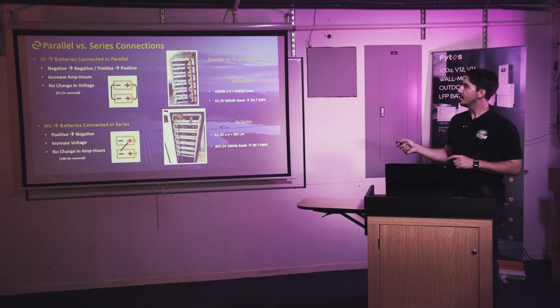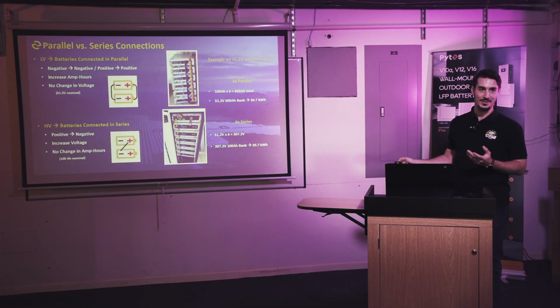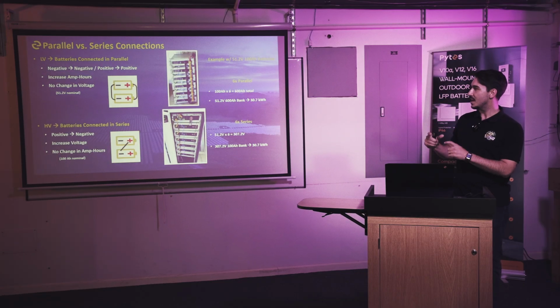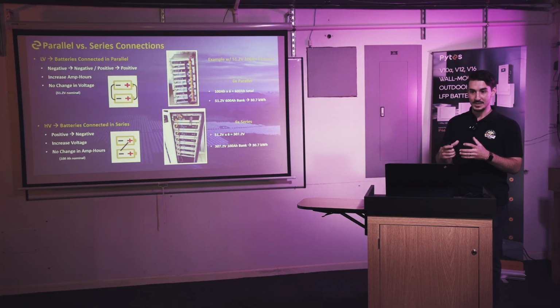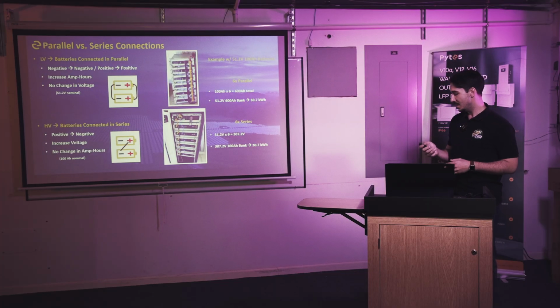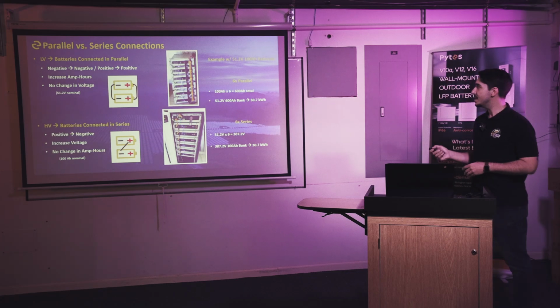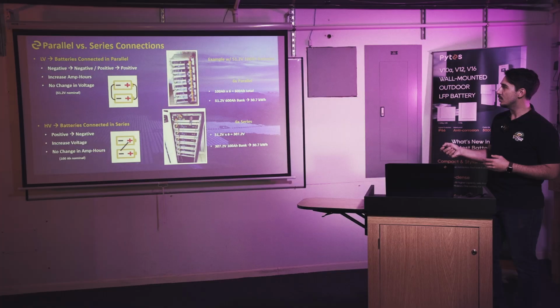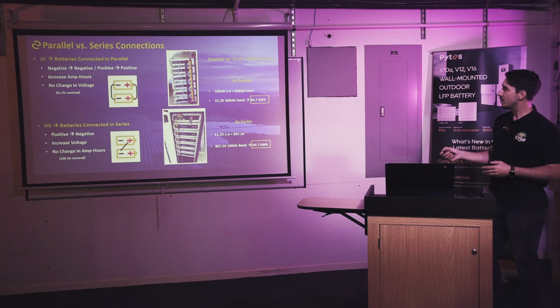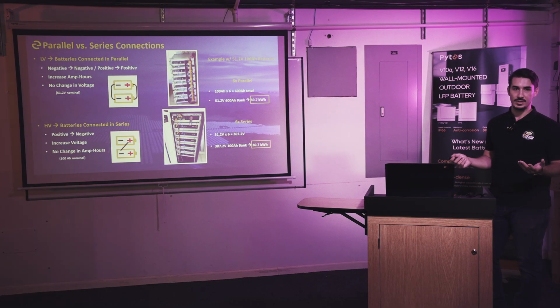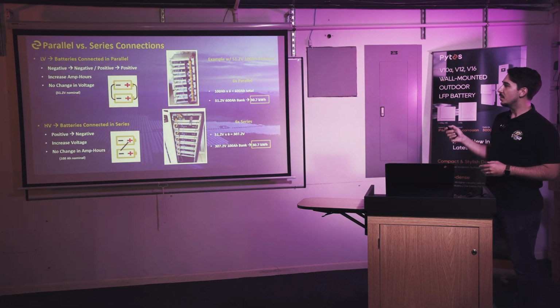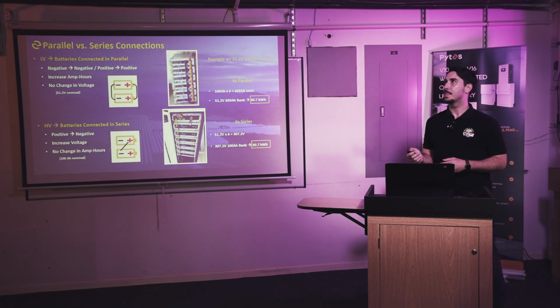Now, to be clear, you cannot connect V5 batteries in series and you cannot connect the high voltage batteries in parallel — they're two different models, but inside the core of the batteries they're the same. So if you have a 6 battery system, whether it's low voltage all in parallel, or high voltage all in series, your energy is the same in both cases. All that's changing is our amp hours and volts, but it's still 30 kilowatt hours — 5 kilowatt hours times 6, no matter what.